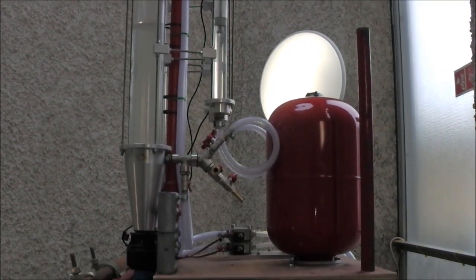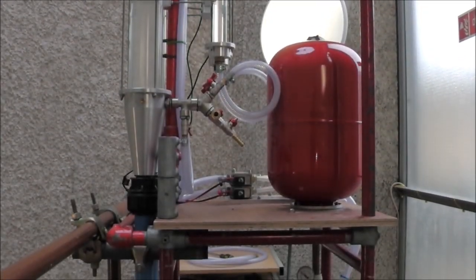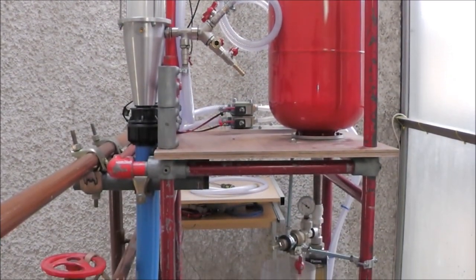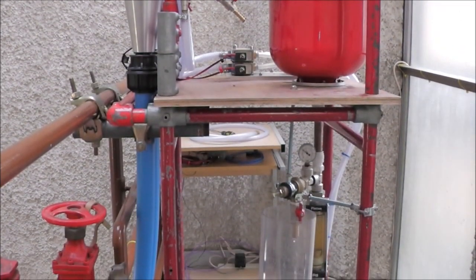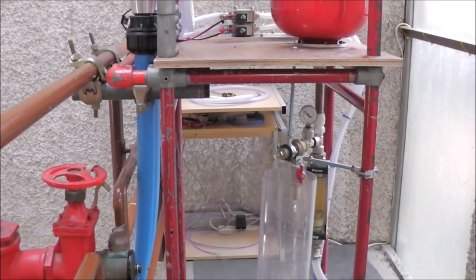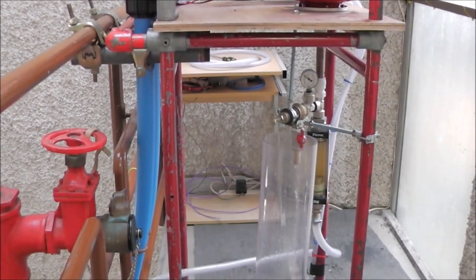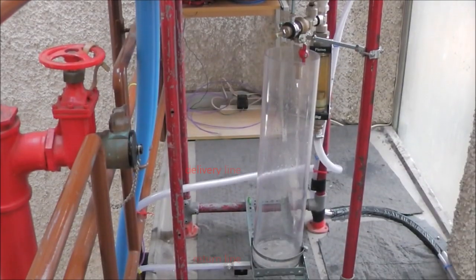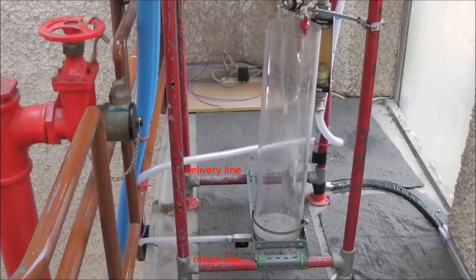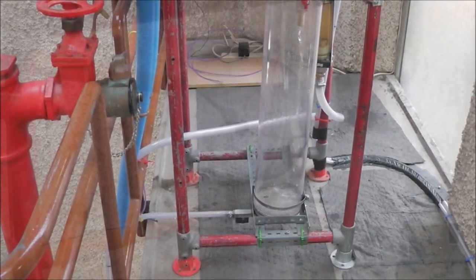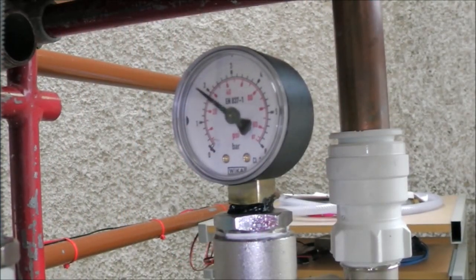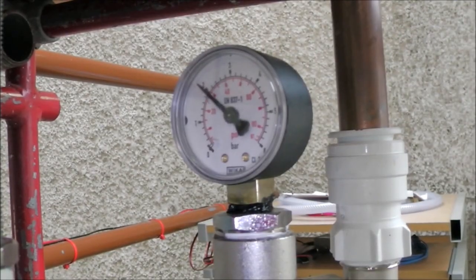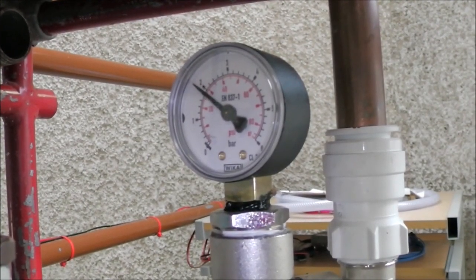As we pan down from the top you see an expansion tank to the right used to smooth the flow and the exit flow coming up the delivery line and being discharged into a separate reservoir. This is then returned to the borehole tank at the bottom with the pump via the return line. Here you can see the additional surface pressurization mentioned earlier of around 1.8 bar which could be used to distribute the water around at the surface.